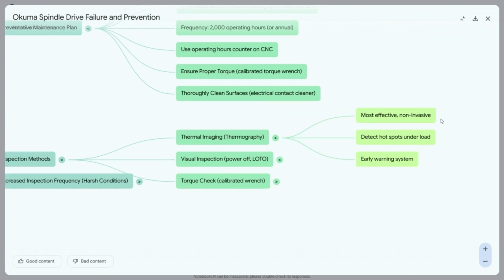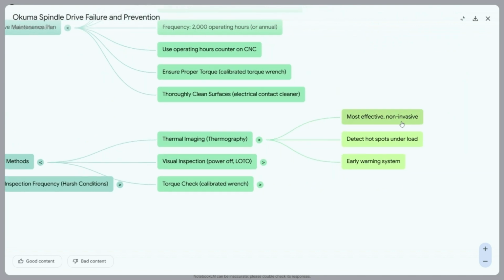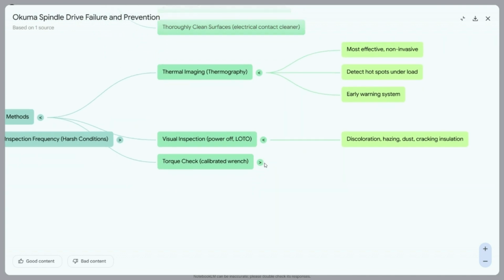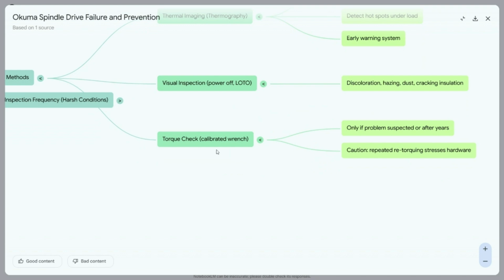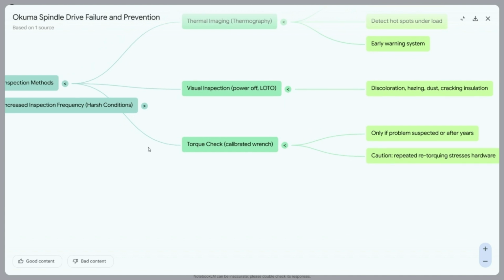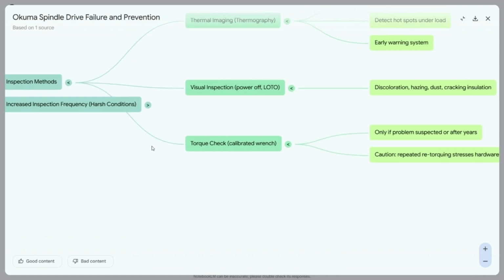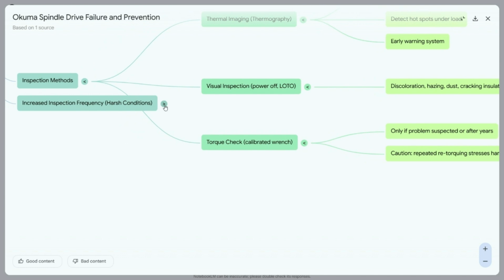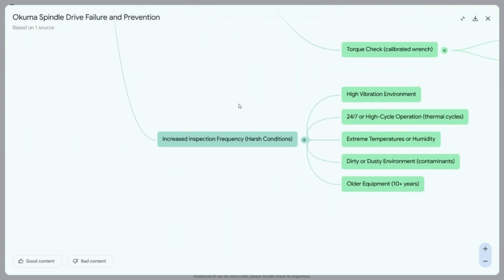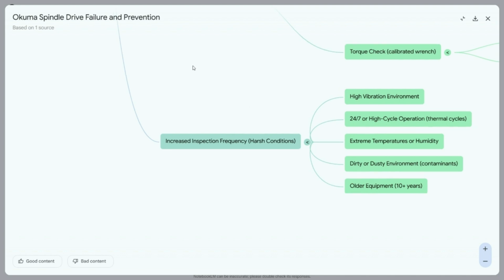Yeah, it's such a vivid illustration of how a truly catastrophic failure, melted cables, a completely burned out drive, can often be traced all the way back to that initial high resistance connection, just kicking off that destructive thermal runaway cycle. And the principle here really extends far beyond just machine maintenance, doesn't it? It's kind of a lesson about complex systems everywhere. It shows how seemingly small, maybe overlooked details, whether they're physical electrical connections, digital interfaces, or even communication links within a team or organization, can have cascading, dramatic, and often very expensive consequences if they aren't properly checked, maintained, and secured.